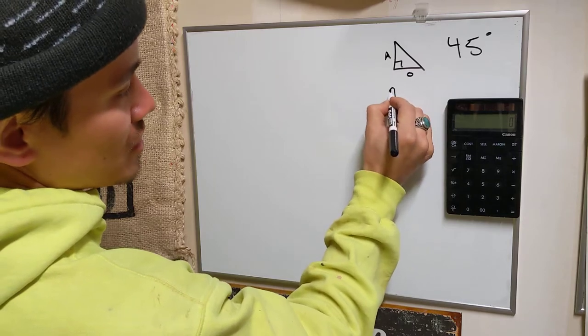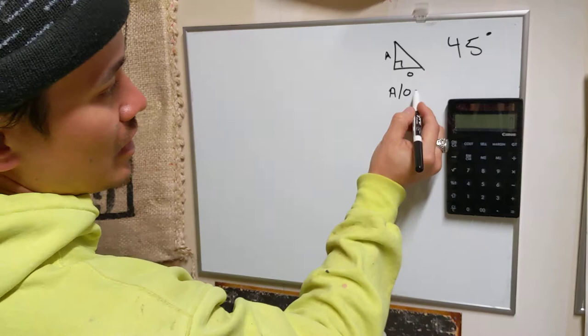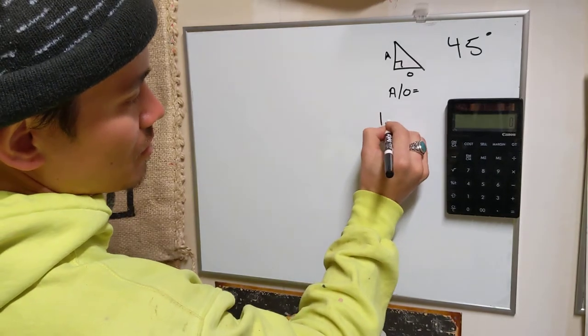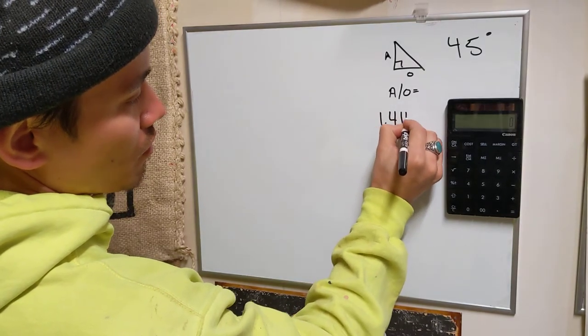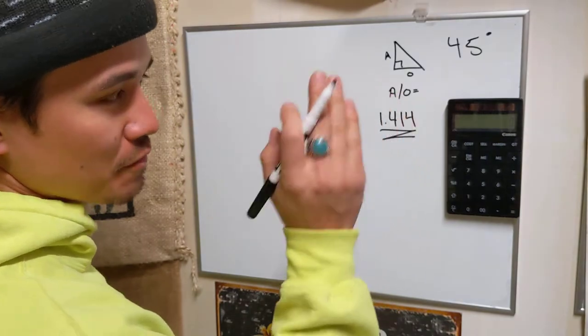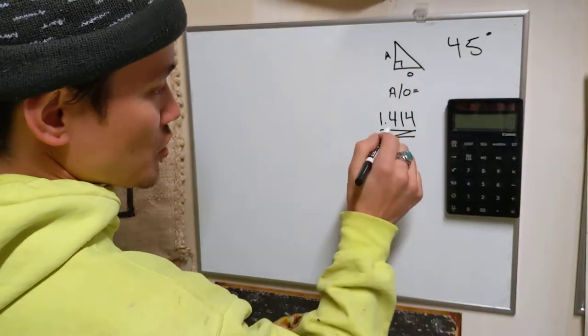So this advance is always equal to this offset. When you see this symbol, it's advance or offset. And you multiply that by the special number, which is 1.414. That is your magic number. That is a number you need to memorize. That is a number that's always going to stay constant. If it's a 45 degree offset, it's always 1.414.